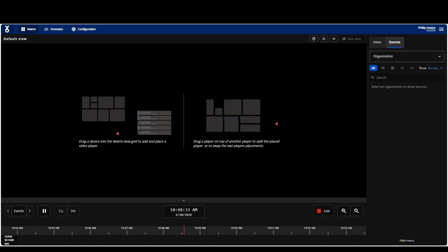Before proceeding, it's important to discuss testing and validation. Modbus devices can vary significantly between manufacturers. Differences in register maps, scaling values, bit order, communication settings, and supported functions can all impact how data is collected and displayed within the platform. For this reason, YourSix strongly recommends thoroughly testing all Modbus integrations before deploying them in a production environment or delivering a solution to a customer.